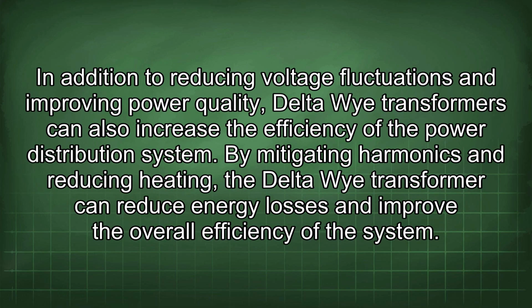In addition to reducing voltage fluctuations and improving power quality, Delta Wye transformers can also increase the efficiency of the power distribution system. By mitigating harmonics and reducing heating, the Delta Wye transformer can reduce energy losses and improve the overall efficiency of the system.